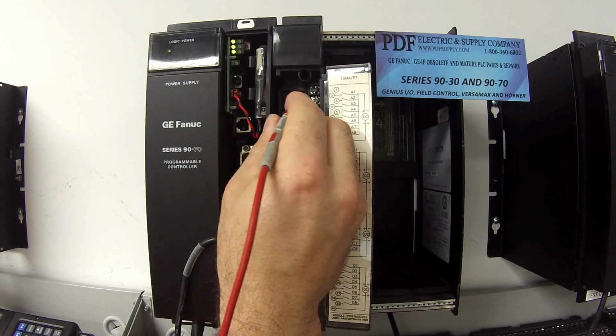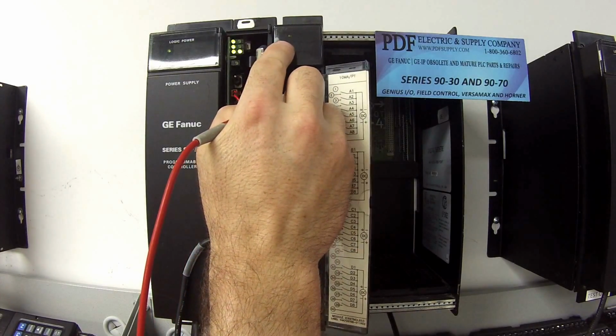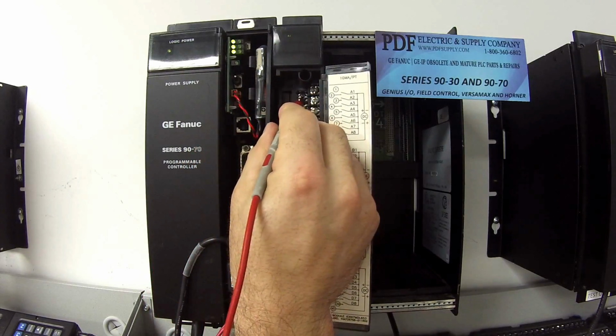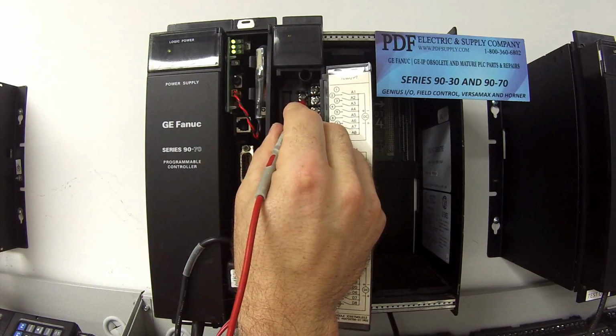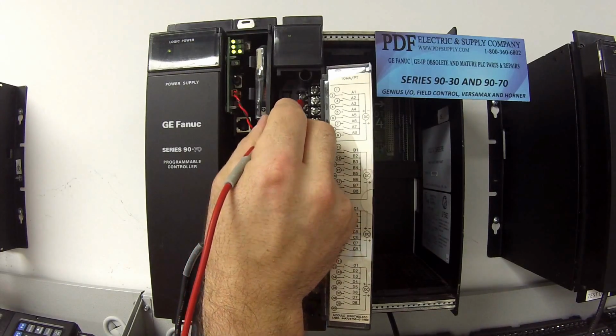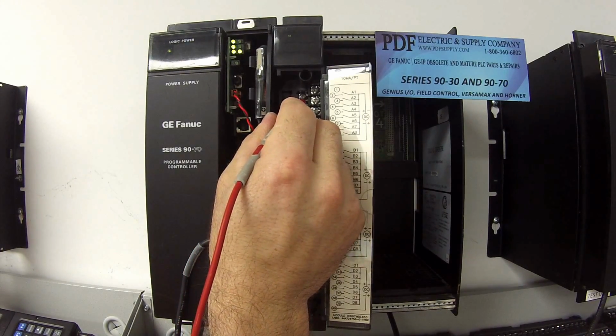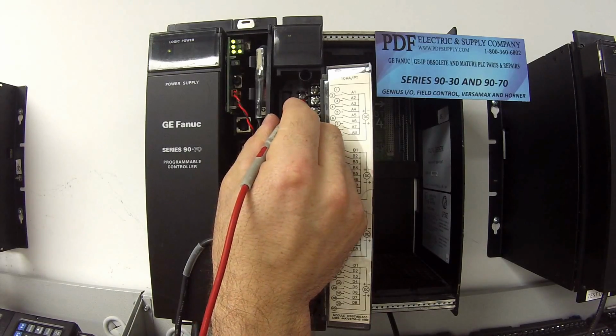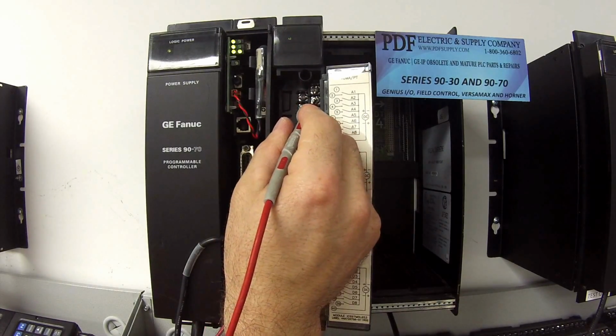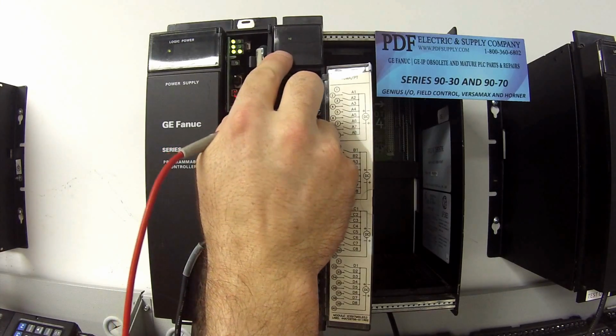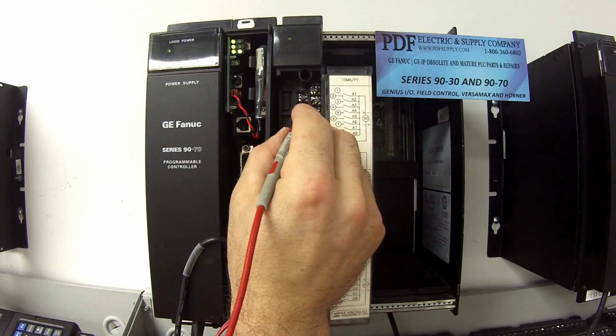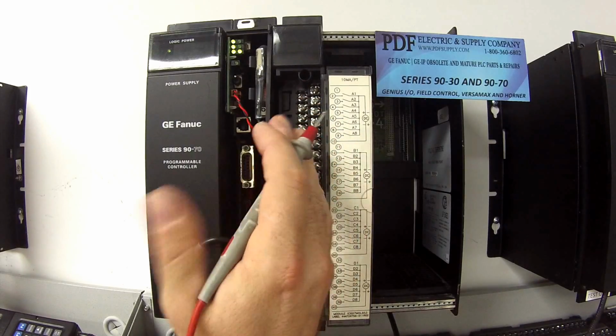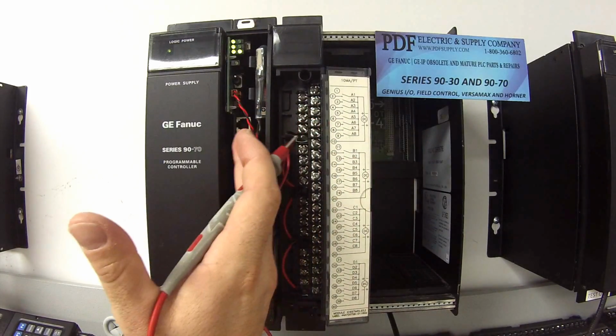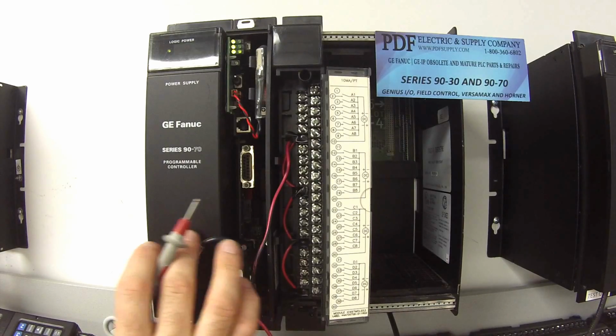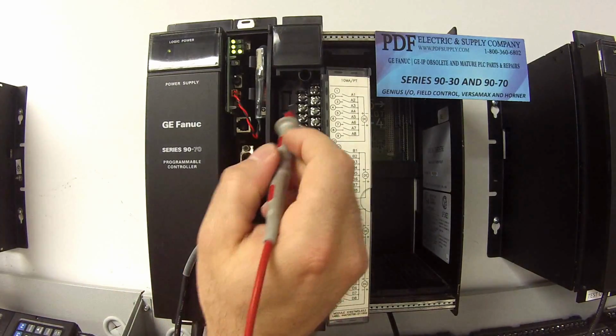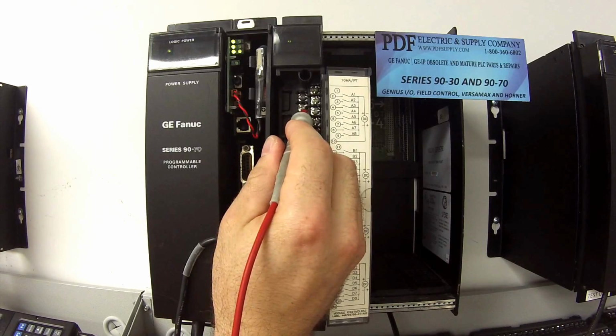As I probe each channel, you'll notice the LED behind this screen will turn on, indicating I'm probing channel 1, A1. I'm also paying attention in Proficy Machine Edition to see that the 0 at that channel is turning to a 1. One tip for you: just because these LEDs, here for user reference, turn on, doesn't necessarily mean the information is going from this input module through the CPU to your Proficy Machine Edition program. So it's possible the light could come on and you actually have a faulty channel.